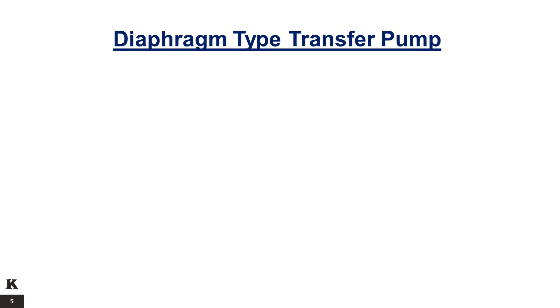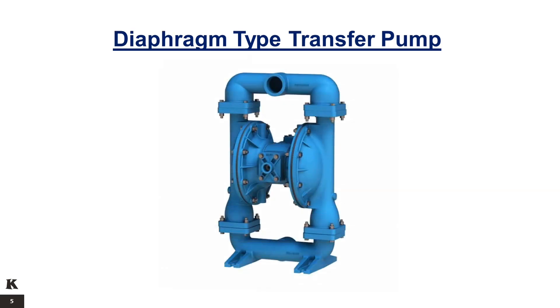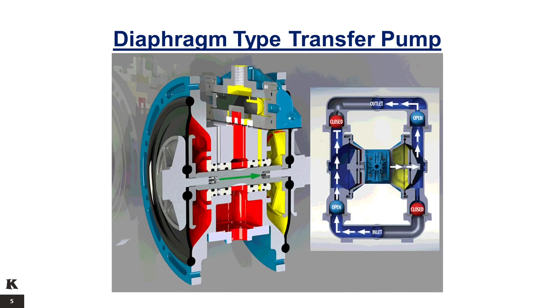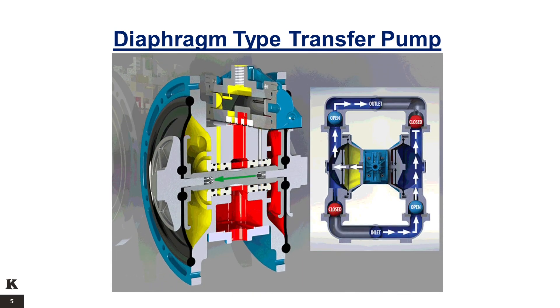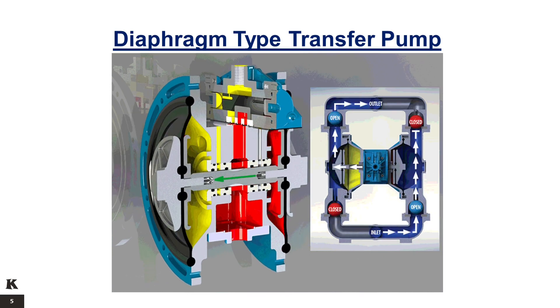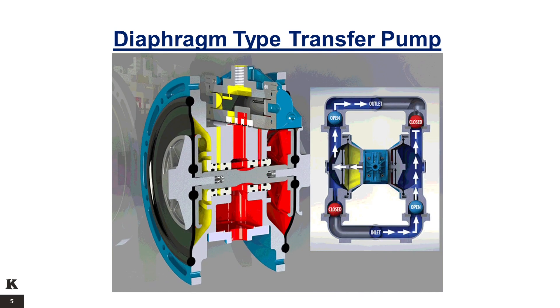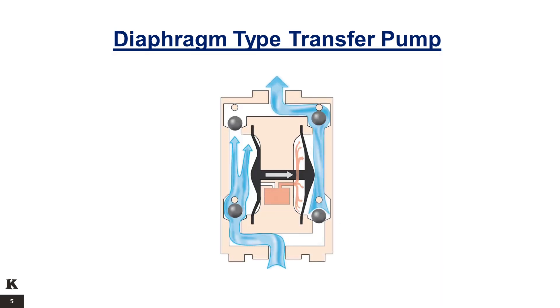Diaphragm type transfer pump. A diaphragm pump is a type of positive displacement pump that uses a combination of the reciprocating action of a rubber or Teflon diaphragm and suitable non-return check valves to pump a liquid. Sometimes this type of pump is also called a membrane pump. A double diaphragm pump, or an air-operated diaphragm pump, uses compressed air as a power source.